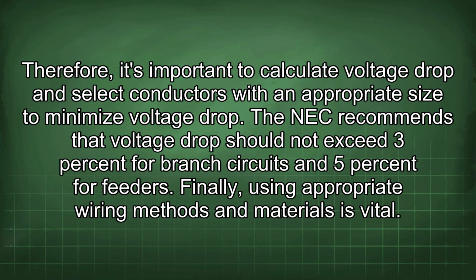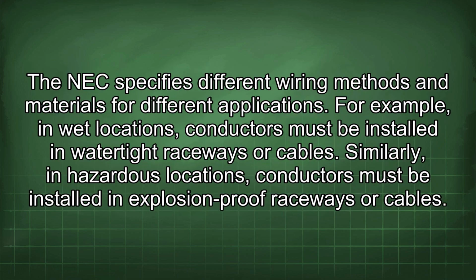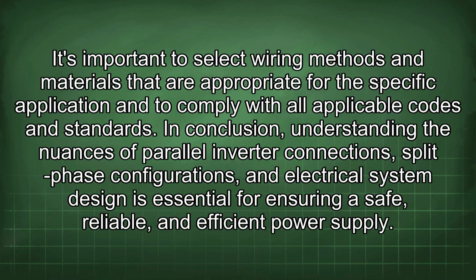Finally, using appropriate wiring methods and materials is vital. The NEC specifies different wiring methods and materials for different applications. For example, in wet locations, conductors must be installed in watertight raceways or cables. Similarly, in hazardous locations, conductors must be installed in explosion-proof raceways or cables. It's important to select wiring methods and materials that are appropriate for the specific application and to comply with all applicable codes and standards.